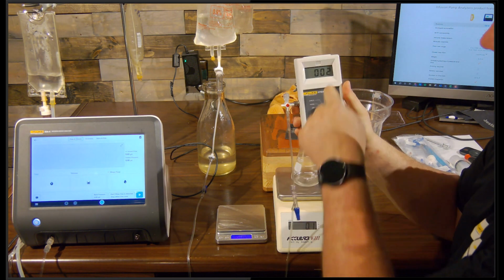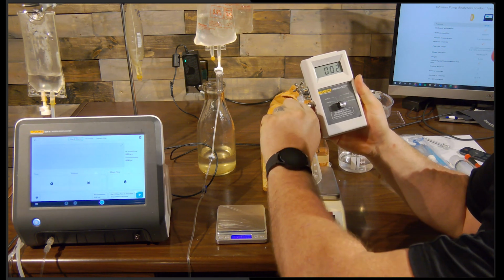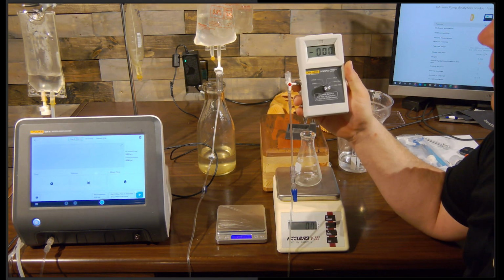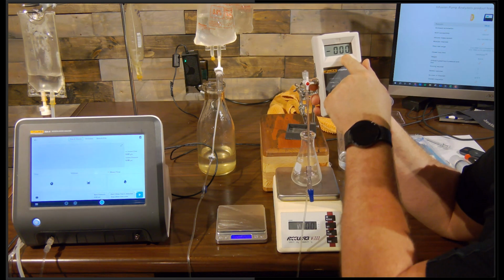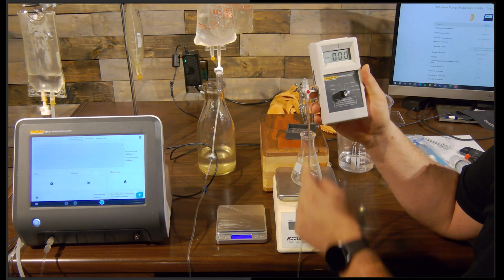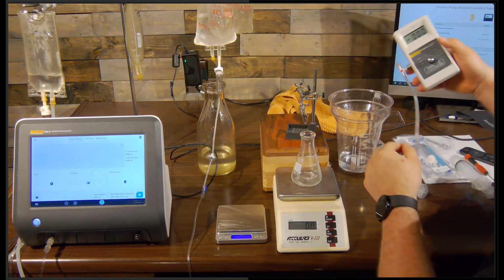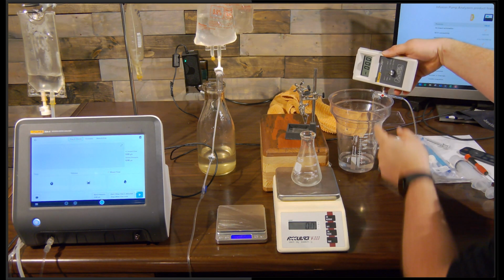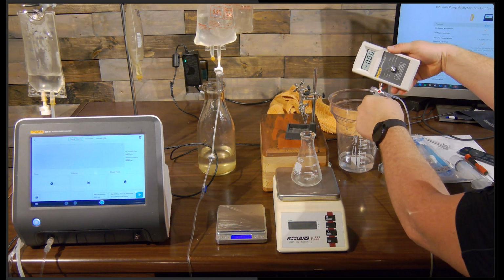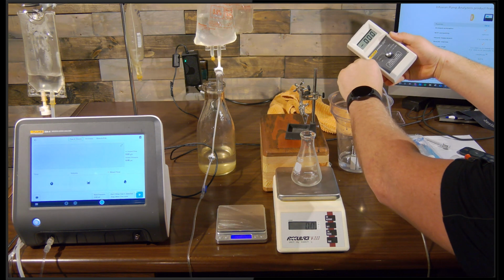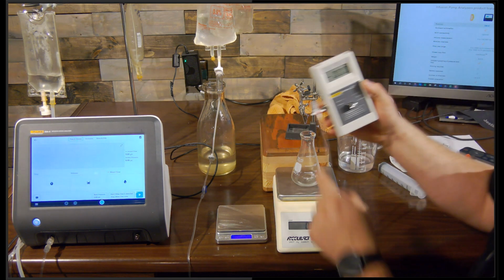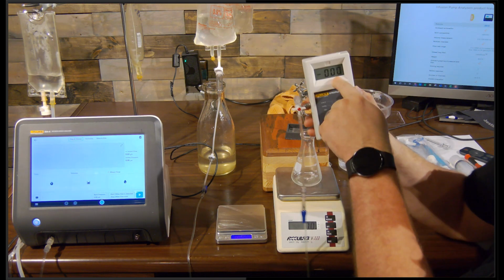All right, now I introduce pressure, so I have to turn this stopcock ball valve until I read atmospheric pressure, in which case I would do my priming sequence, and I need to hold this over a container like this, and it would prime in and the drops would come out, and then when I'm ready, turn this valve. And it's going to build up pressure here, and I would read that max pressure.